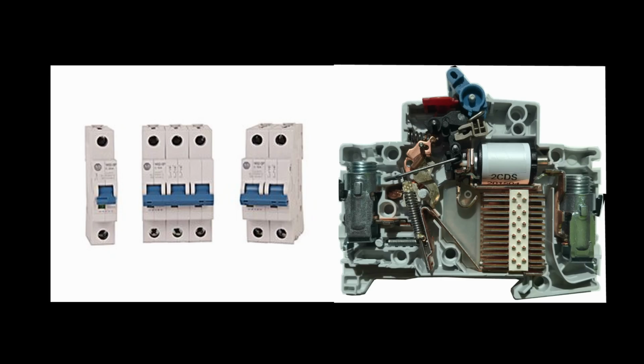But with the recent industry shift from 120 volt AC to a safer 24 volt DC as the voltage of choice for control circuits, we've had to develop a more appropriate type of electronic circuit protector, or ECP as they're known, that meet the demands of this low voltage circuitry. Why is that? Well, miniature circuit breakers are electro-mechanical thermal devices that are designed to function on AC power networks that supply an infinite amount of current from a power utility. They're not designed to function effectively in a 24 volt DC power circuit.